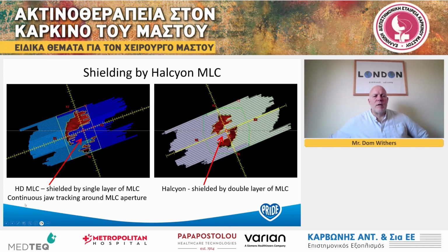by an HD MLC. So this is what we have on our Edge. This has 1/4 centimeter leaves in the middle sections and 1/2 centimeter leaves on the outside. And you can see that the jaws are meeting the aperture, but there is only one set of MLC shielding in this region here. So you have this leakage of around 1.5% coming through here.